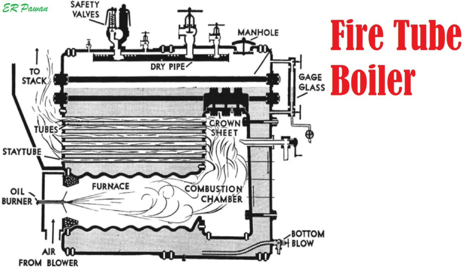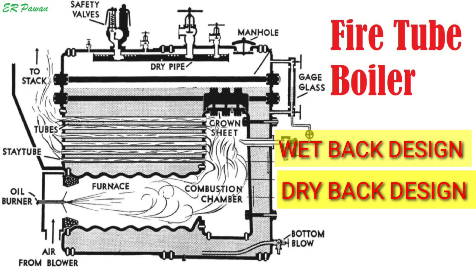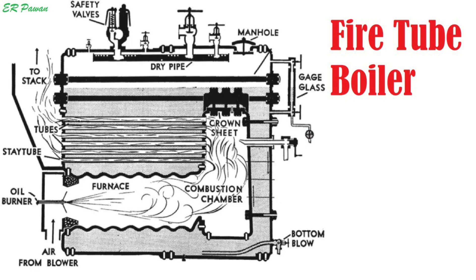In fire tube boilers there are two kinds: one is the wet back design and another is the dry back design. In wet back design there is a water wall at the back of the boiler in the area where combustion gas reverses direction to enter the tubes. In dry back designs, refractory is used at the back instead of a water wall. With the water wall, internal maintenance is required, but refractory replacement is expensive, and overheating, gauging and cracking of tubes at the entrance to return gas passes are common problems.